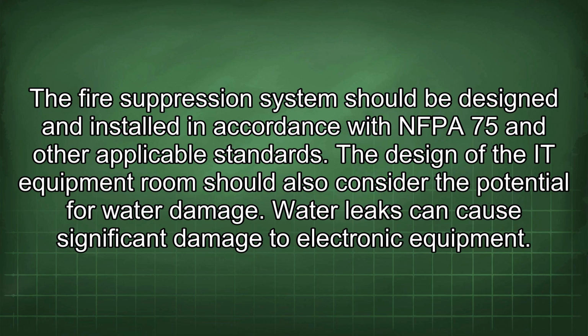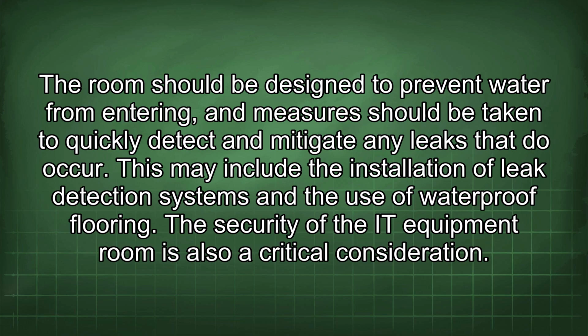The design of the IT equipment room should also consider the potential for water damage. Water leaks can cause significant damage to electronic equipment. The room should be designed to prevent water from entering, and measures should be taken to quickly detect and mitigate any leaks that do occur. This may include the installation of leak detection systems and the use of waterproof flooring.